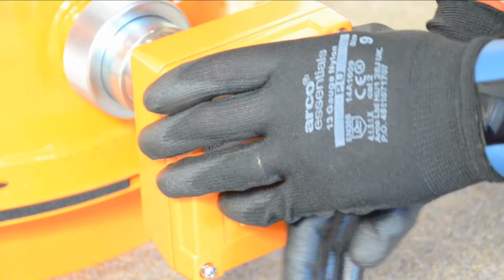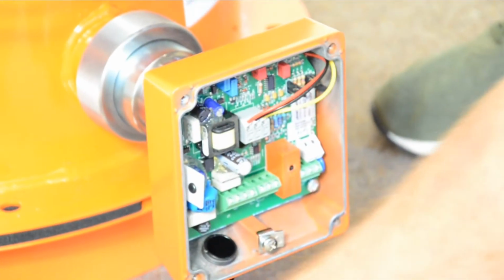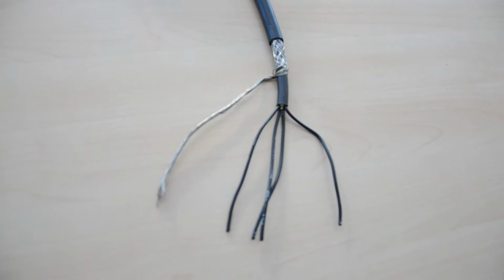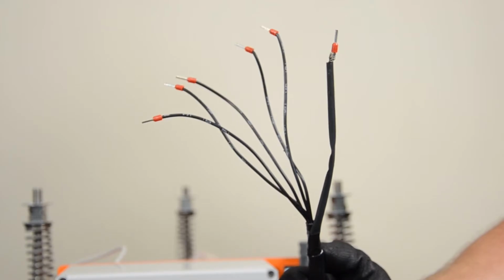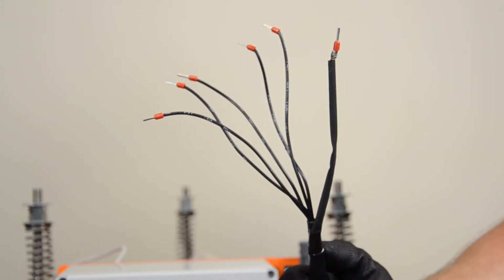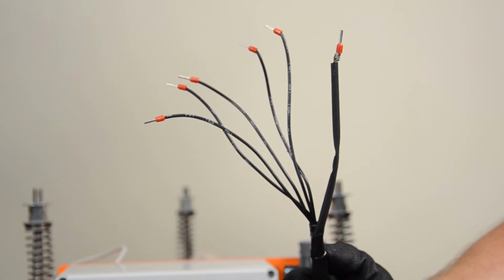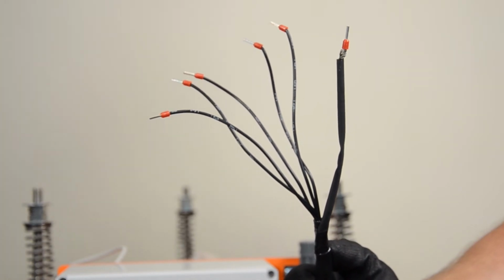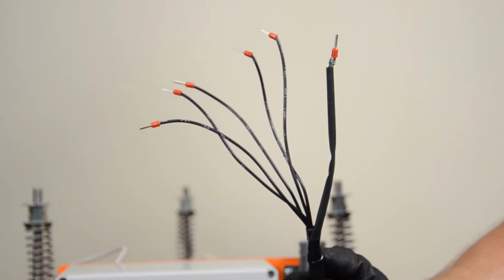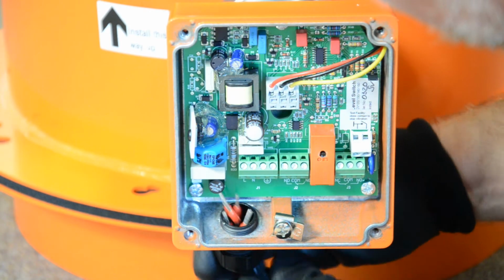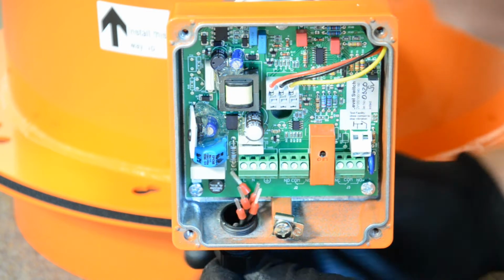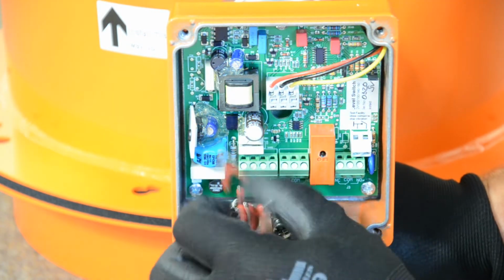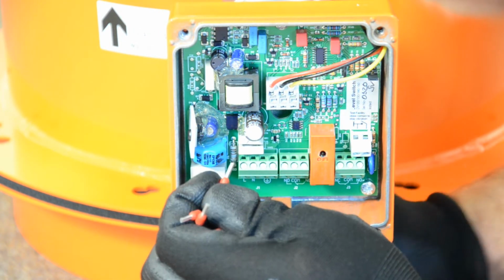Remove the level probe's cover. Please note, use screened cable as shown here. Wire the level probe with a 5-core screened cable. We have covered the extra core with a black heat shrink to prevent contact with any metal. The high-level alarm is linked to TB7. This is the factory default for a single level probe installation. Insert the cable through the connection port.